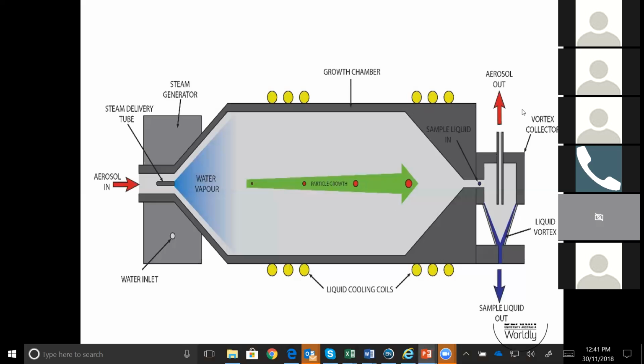To mention here, this is the solvent resistant vortex collector. In principle, the design of this system is similar to that of a mini PM cyclone. However, while the cyclone design focuses on the cutoff size and shape, this vortex collector is predominantly concerned with the formation of a stable liquid vortex within this cone. We spent a lot of time designing the collector dimensions.